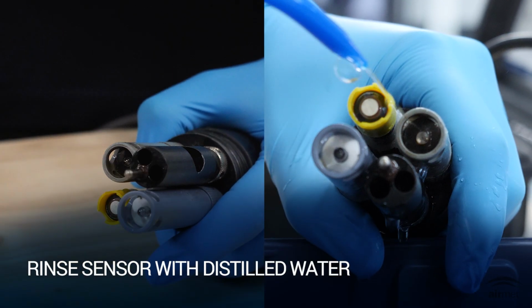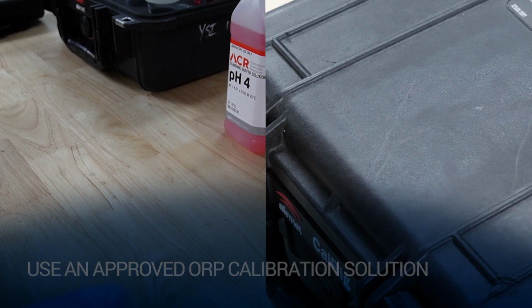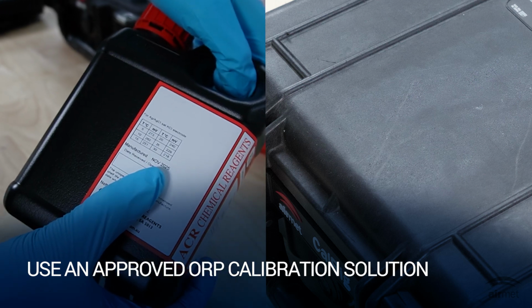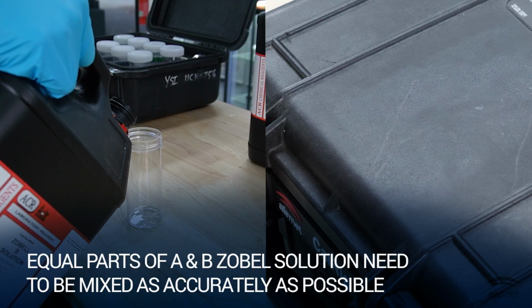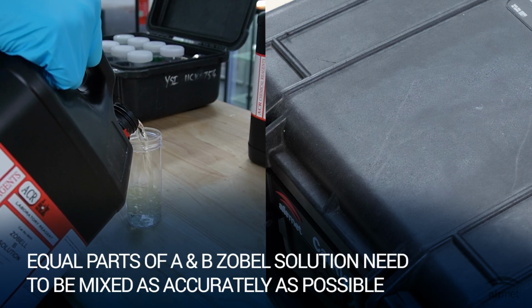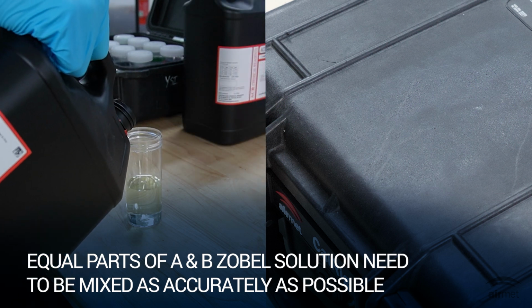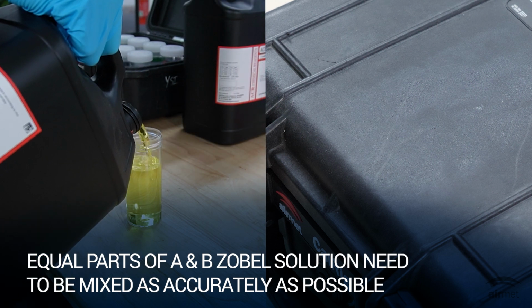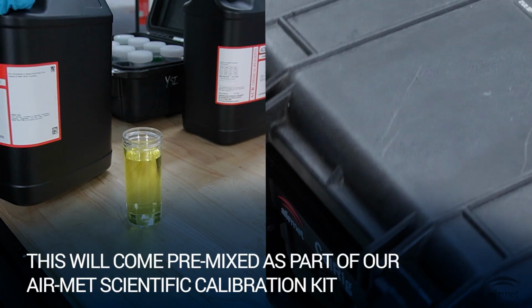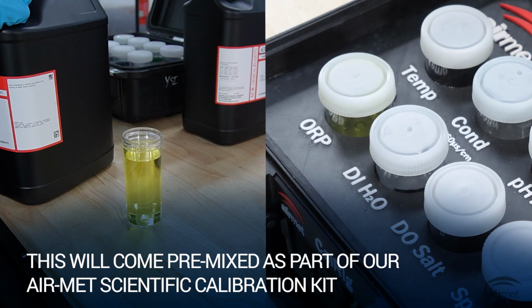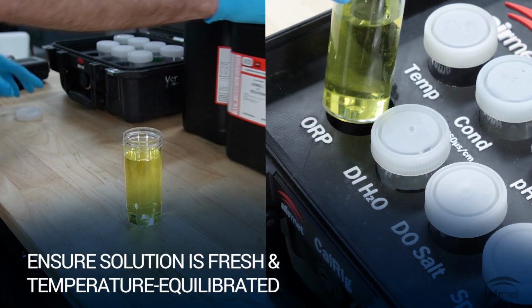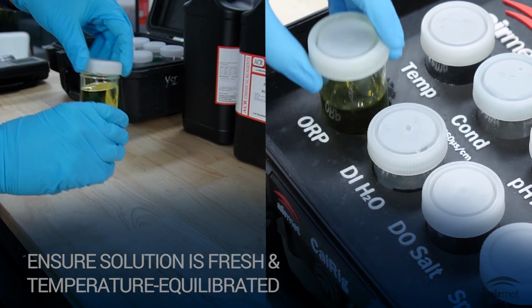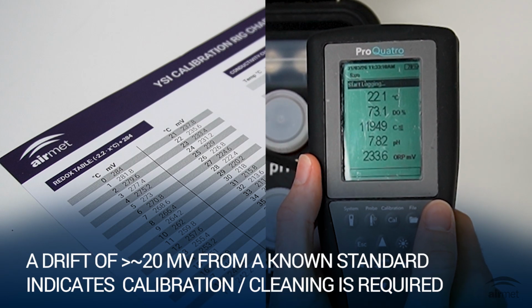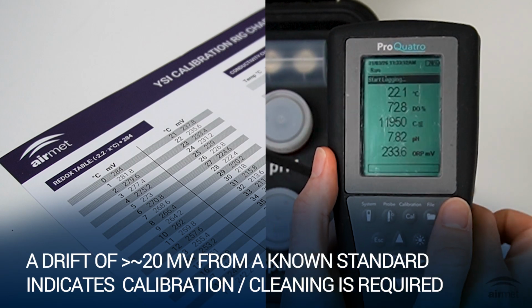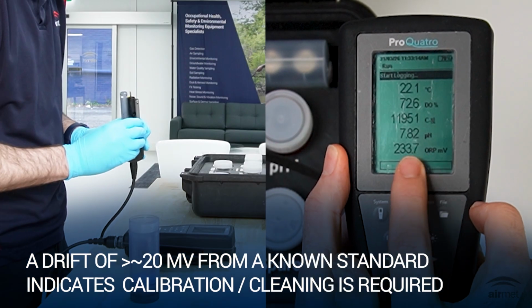Rinse the sensor with distilled water. Use an approved ORP calibration solution. Part A and Part B Zobel solution needs to be mixed as accurately as possible. Do your best to measure exact quantities of both A and B solution. This will come pre-mixed as part of the AirMet scientific calibration kit. Ensure the solution is fresh and temperature equilibrated. A drift of more than around 20 millivolts from a known standard indicates that calibration and/or cleaning is required.